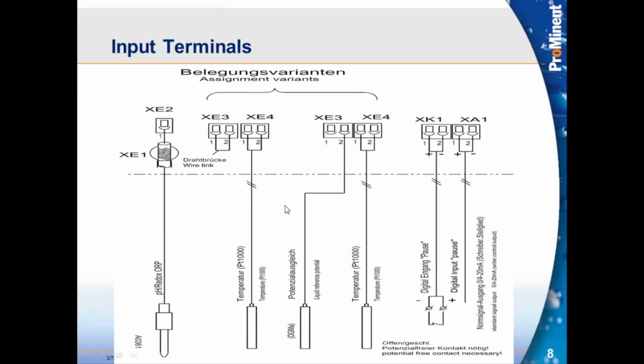So what we do is we run a wire into number 2, and we pick up that electrical noise that is in the processed water, or in the sample water stream anyway. We have an assembly for the DGMA, we can do that, or we can maybe clamp it to a pipe to get that signal in. But once we have that reference, now the sensor can measure a more true signal to what we need to pick up. Then again, our temperature sensor is on XE4.